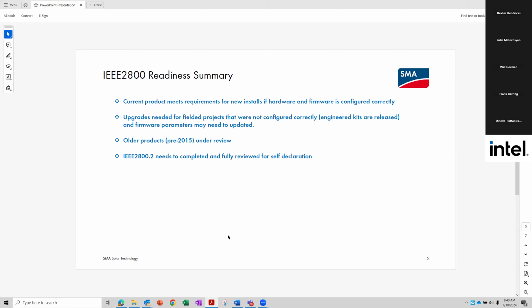Summarizing SMA's readiness for IEEE 2800, we can generally confirm that our current products will meet the requirements for all new installs. Just have to select the right options in the hardware and set the correct parameters in the firmware. So if you have a properly configured inverter setup, then our current products, we feel very confident, will meet the IEEE 2800 requirements. On our installed base, some upgrades are needed, like the transient overvoltage ride-through requirement, which is new. That's a hardware upgrade that has to happen if that option was not pre-selected, and firmware updates and parameter adjustments have to be made for our installed base.